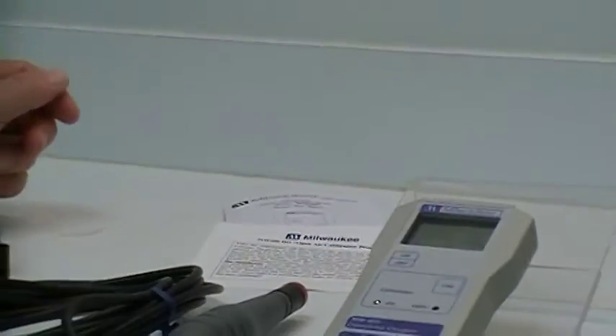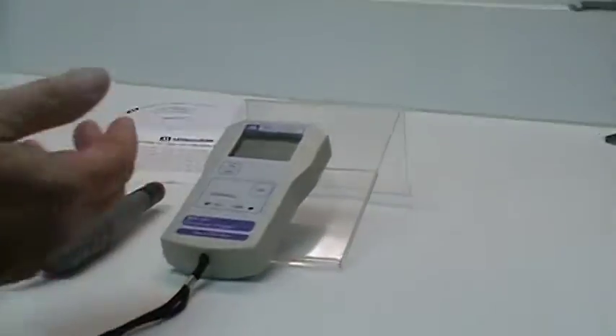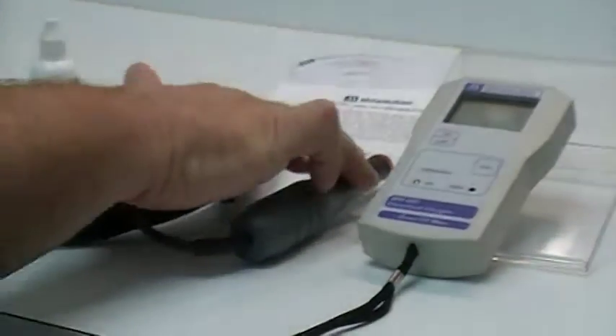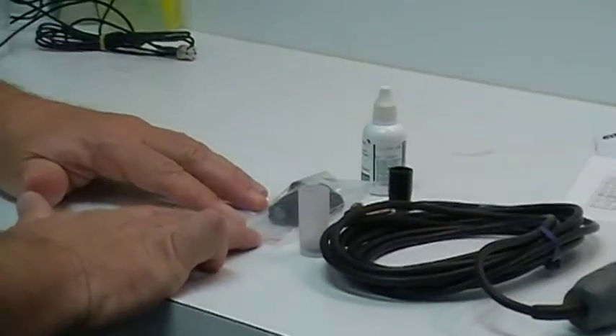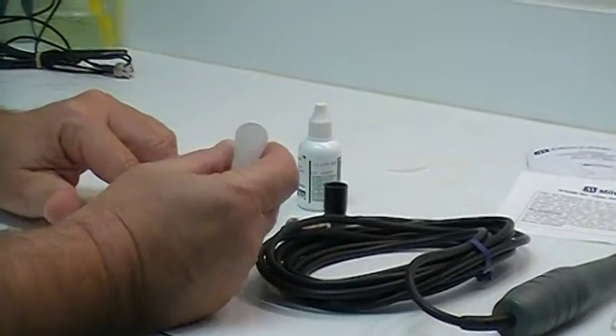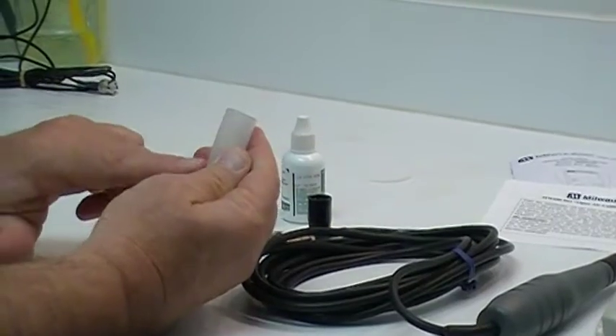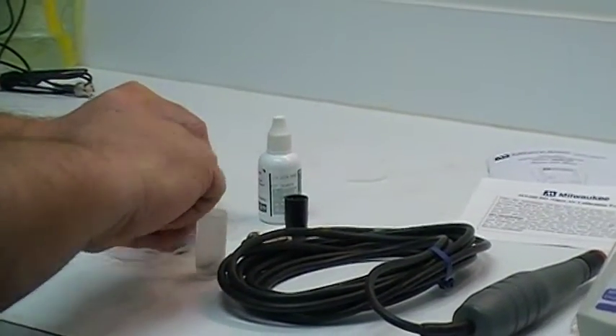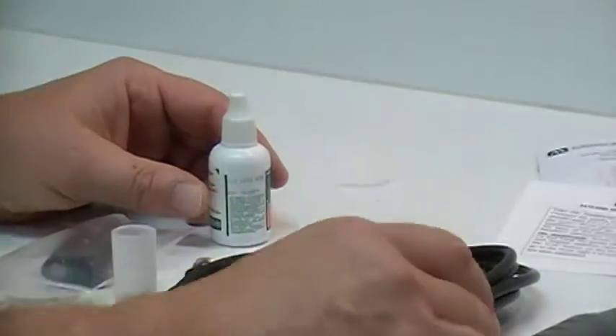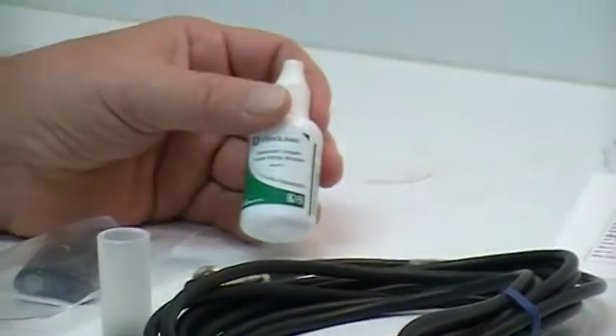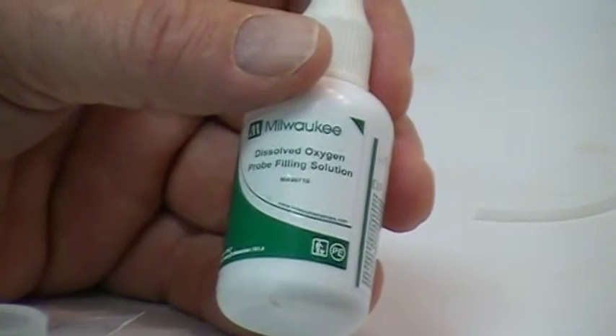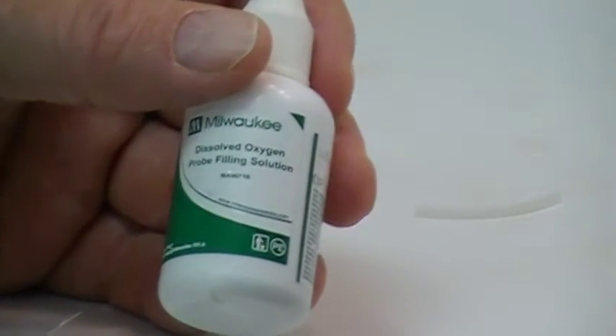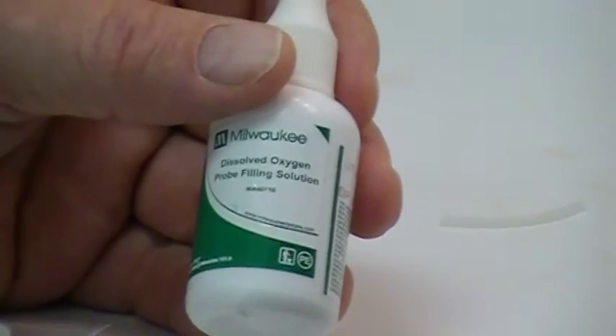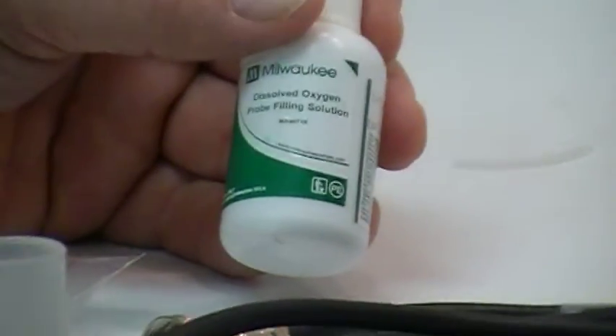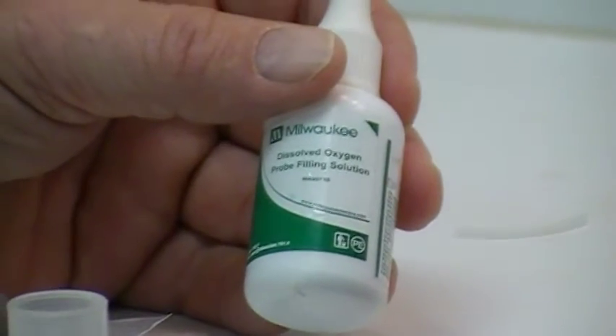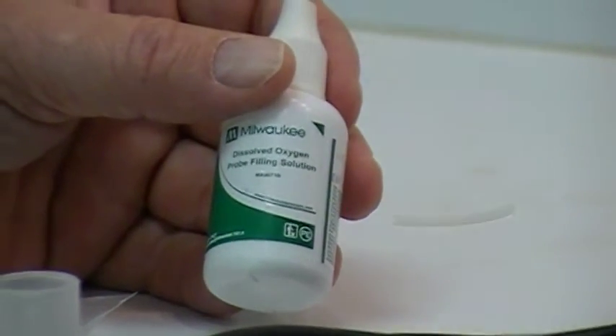When you first open up the unit, these are the parts you see. You've got the base unit, we've already put the battery in. You have the probe with a protective cap on. You have a package of 5 membranes. In the membranes there's also a protective cap with extra O-rings. I've already sorted out one of the membranes we're going to be using, and you have a starter bottle of MA9071-S, which stands for starter bottle, that will provide you with possibly 3, maybe 4 refills of your membrane. At some point you're going to need to purchase additional MA9071 electrolyte solution.